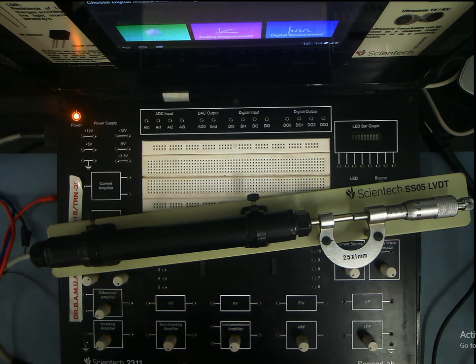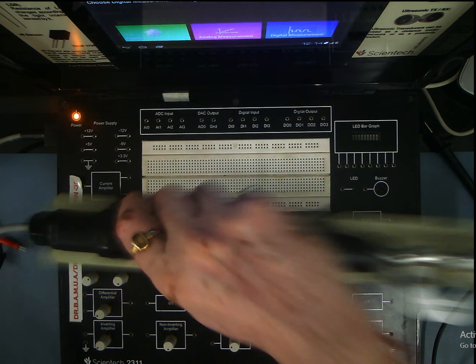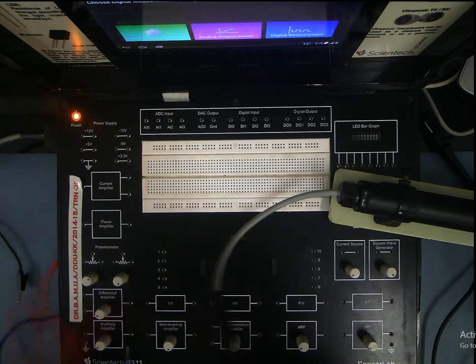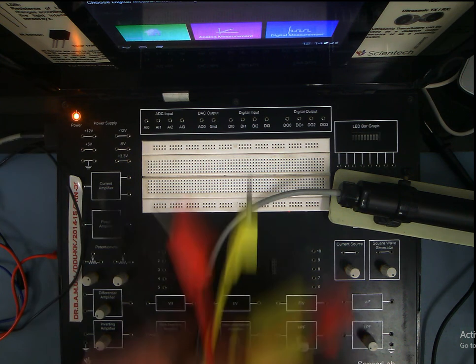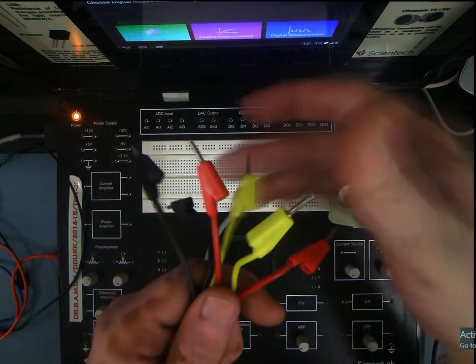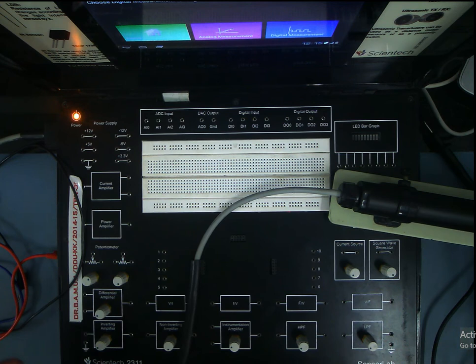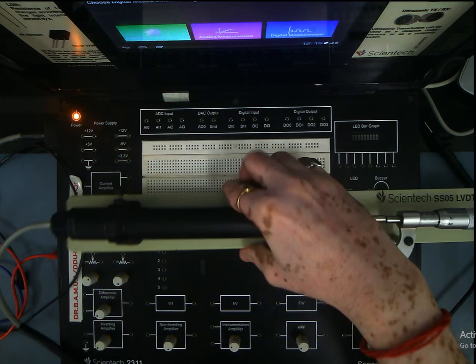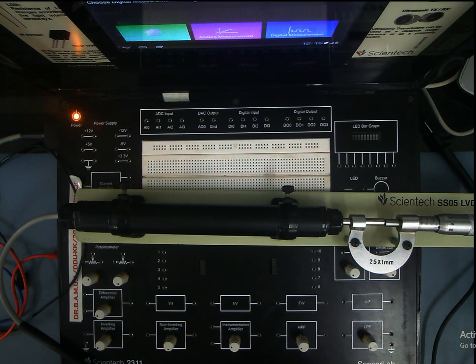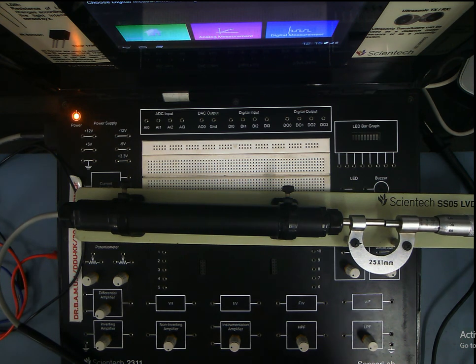Now let us see how many terminals there are. It is a bit difficult to show everything, but you can see this wire coming out of the LVDT, and we can very easily find that there are 6 wires: 2 yellow, 2 red, and 2 black. Why 6 wires? Very intuitively you can say that 2 wires are for the primary winding, 2 wires are for secondary 1, and 2 wires are for secondary 2. Absolutely correct.